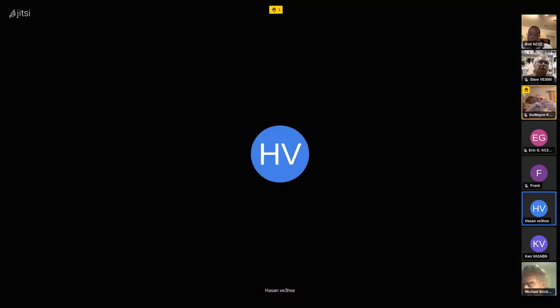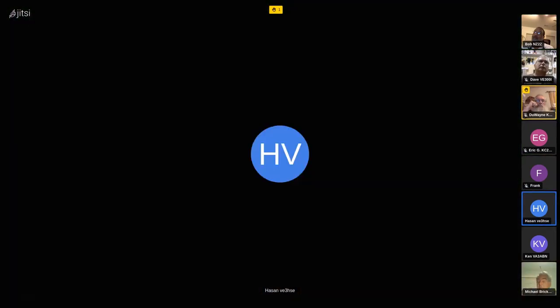Well, I'm not an expert on this, but I understand the point that if you did a 900 megahertz range, the device will interpolate between the calibration points. So it's some kind of average, and it's not as accurate - put it this way, not as accurate as if you do your 400 points or 100 points on, say, the 40 meter band, which is 300 kilohertz. You're going to get quite a number of calibration points in there, so the spacing between them will be small. So yeah, I would calibrate it every time - that's what I do.